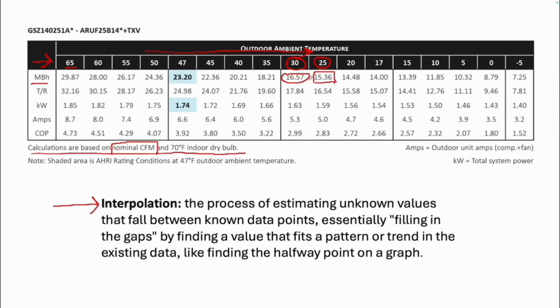Now, typically manufacturers will tell you that, as long as you're within 10% of what the product data says the system can do, they consider that acceptable. Again, I'm just giving you the down and dirty quick on this, but once you start looking through these kinds of documents, you'll find there are also correction factors. If you have a CFM that is below or above this, they may have a correction factor where they'll tell you to multiply the BTUs by 0.98 or 1.03, depending on whether the airflow is higher or lower.